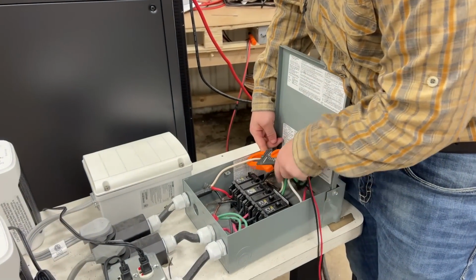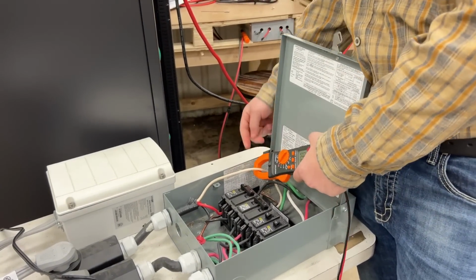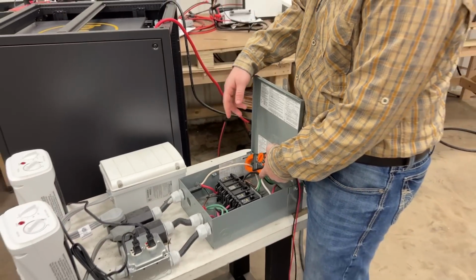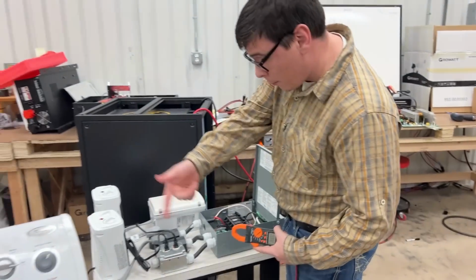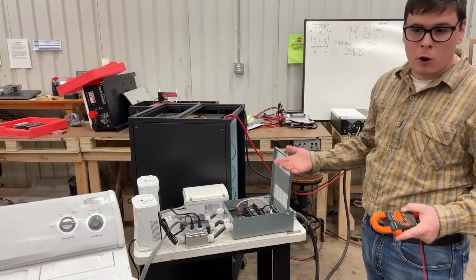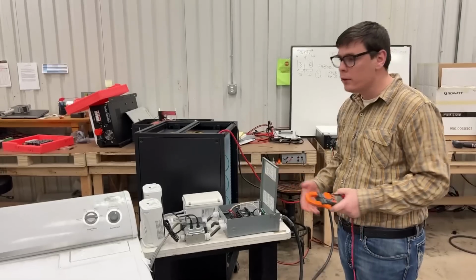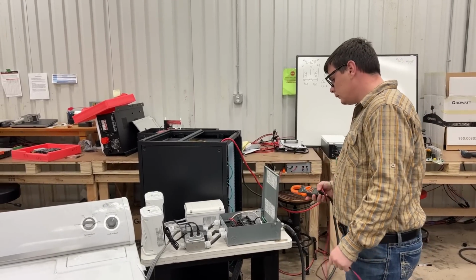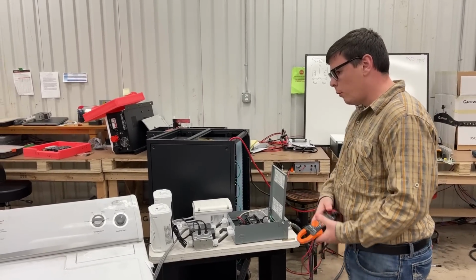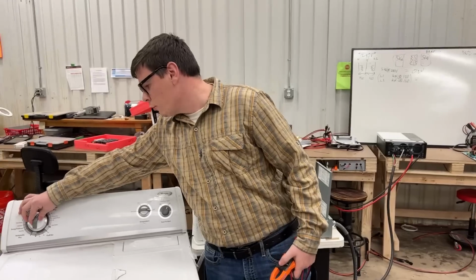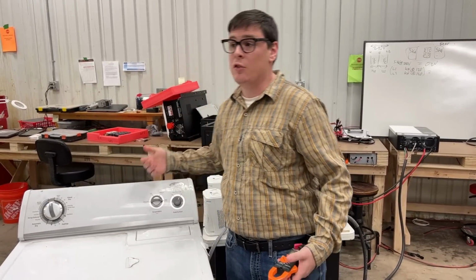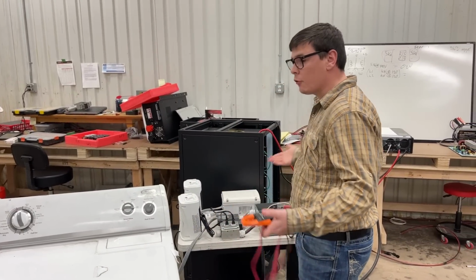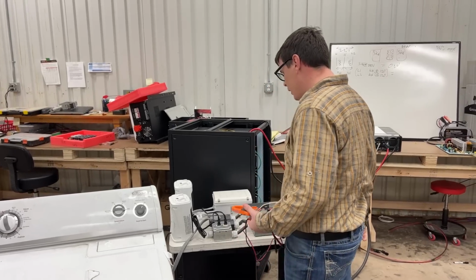And the amperage on neutral is 3 amps. That's just basically the amps needed to run the fans and the motor inside of the thing. But the vast majority of the power here is 240 volt. So just sort of showing that, I'm going to turn this off. That's a 240 volt load. If it was the air conditioner, it'd be straight out 240. We wouldn't even need the 120.